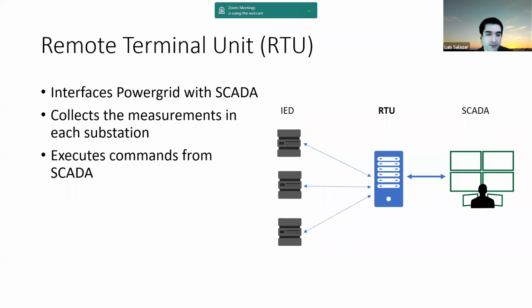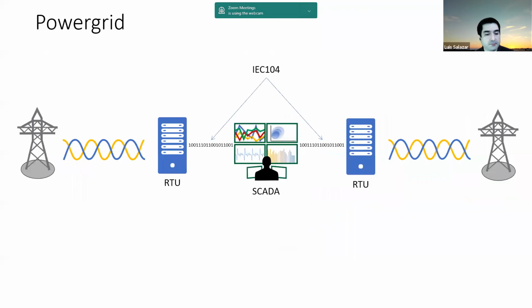This control is used by the remote terminal units that make an interface between the SCADA system that the operators use to control the system and the actual electronic devices that are in the substations that change the topology and make the necessary adjustments to regulate the power consumption, generation, and transmission from the users. And these devices execute every command that is sent from the SCADA system, affecting the power grid itself.